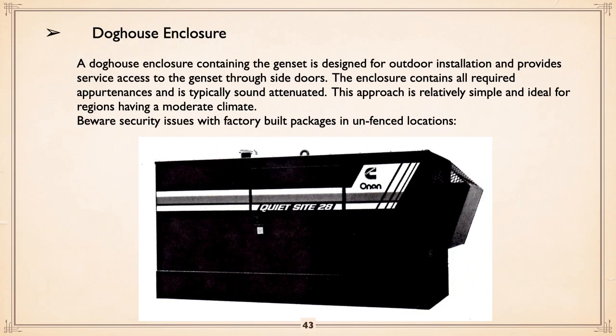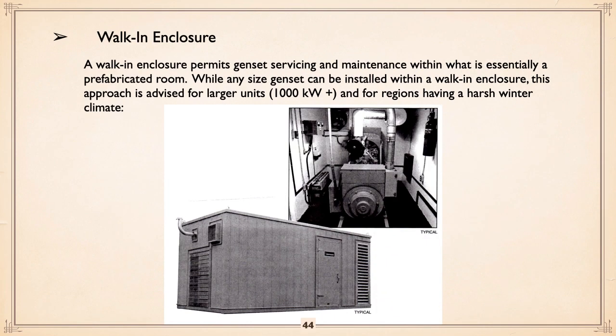Doghouse enclosures. Basically, the genset is designed for outdoor enclosure and installed within a doghouse, as they call it, which has service doors on the side, has all the stuff you need in it, and is sound attenuated. Installations are always simple and ideal for regions having a moderate climate, because you're going to be servicing in the wintertime just as well as in the summertime. Beware security issues with factory-built packages in unfenced locations. In other words, if you've got a vandal area, you don't want them near something like this. See the little cap on the top of the exhaust? Kids can climb up on top of it and drop gravel down into the exhaust. Real easy, okay? Next step up, you can get doghouse enclosures that are not done by the factory, that are custom built and are vandal proof.